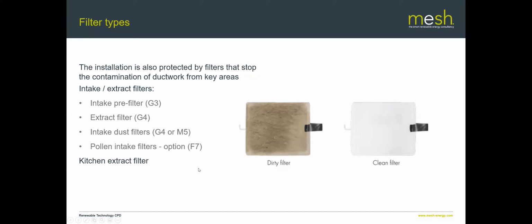It's also important to have an extract filter on the kitchen. So where you've got your extract in the kitchen, that would generally just be a G3 dust and grease filter, and that just means that any sort of grease or dust that's being generated in the kitchen doesn't end up coating the inside of the extract ductwork.